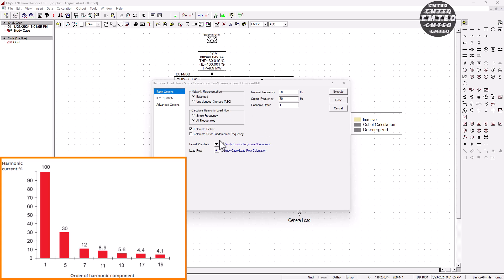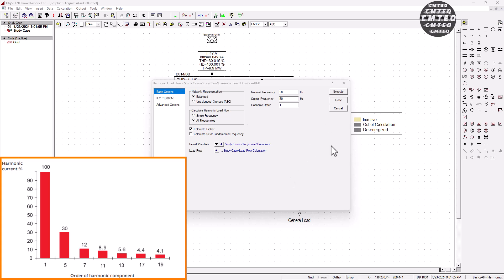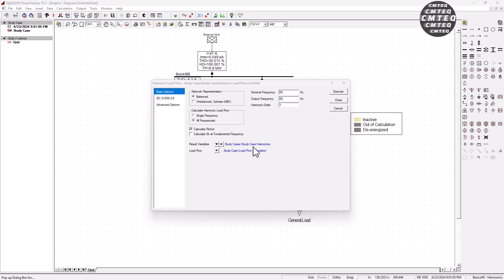The third point is the system response in the harmonics calculation. A generator with a higher impedance can shift the system response closer to dominant harmonics — basically the higher-order harmonics, maybe the 5th, 7th, or 11th harmonic. When this happens, these harmonic currents amplify further, increasing the THD at the particular bus bar. In contrast, a lower impedance on the generator shifts the resonant point away from harmful harmonics, reducing the potential for amplification which would otherwise result in a higher harmonic distortion on the system.